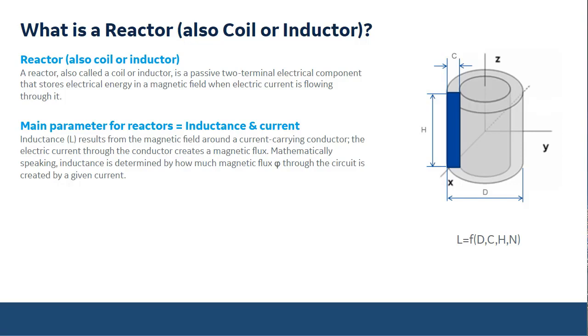And lastly, the environmental conditions. That's very important because we have reactors that are installed in Brazil, which is a tropical place. We have reactors that are installed in Saudi, which is a desert area. And we have reactors that are installed in Canada, which is a minus 45 or minus 50 C region. So for each one of these regions, there are some special design criteria that we need to follow. And also we cannot forget about 150 miles per hour wind conditions in Florida, or maybe high seismic in California, or even another example, the air core reactors may require some large space to fit them. So we need to know how and where these reactors are going to be installed, so we can then design it to fit your application.